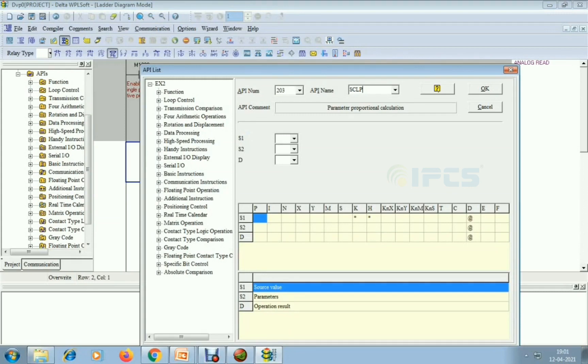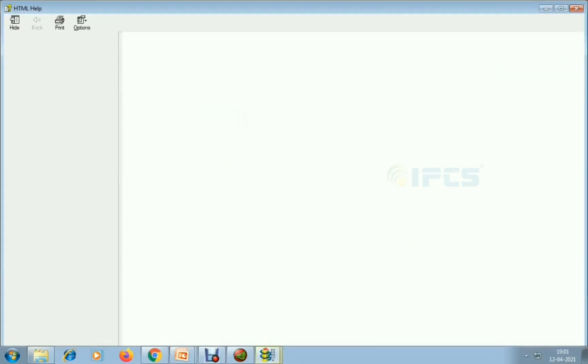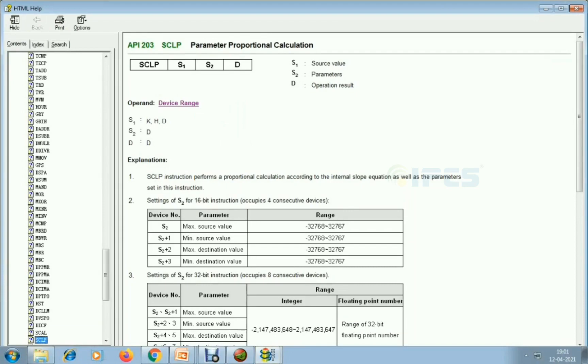SCLP is a parameter proportional calculation instruction, mostly used for scaling input values. S1 is the source input value and S2 is the parameter block — 4 consecutive devices occupy S2. If I give D0, then D0, D1, D2, D3 are used: maximum source value, minimum source value, maximum destination value, and minimum destination value — these are the scaling parameters.